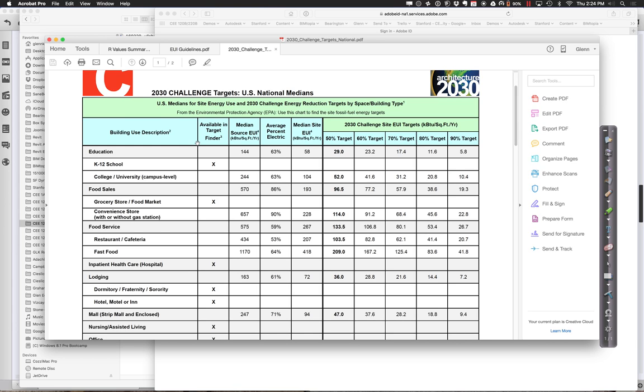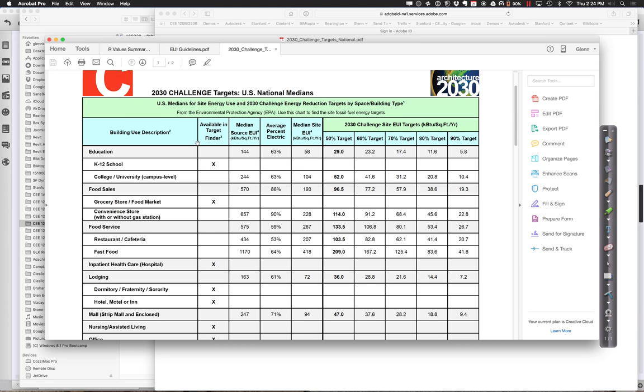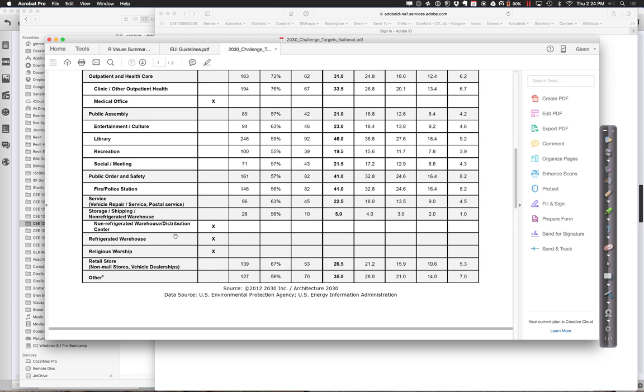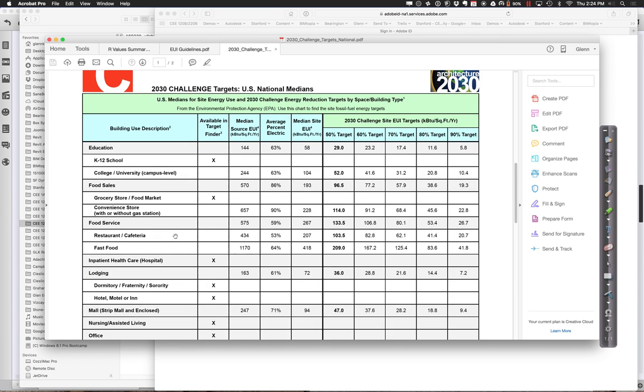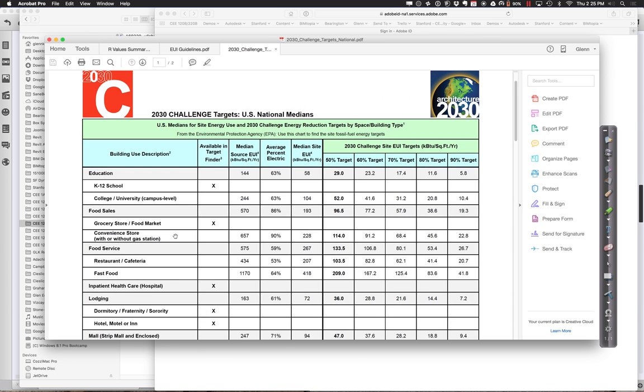If you compare things like the college and university campus versus a fast food joint versus a dormitory, you'll see there's very different numbers that are associated. Lodging at 36, the campus building is 52. Kind of makes sense. We tend to use more than a dormitory. More people, higher occupancy, generating more things. Malls are pretty high. Food service, very high. Fast food, very high. A lot of energy consumed in doing that. So there's targets, and they vary depending on use.